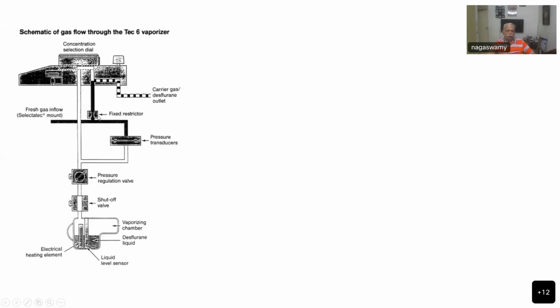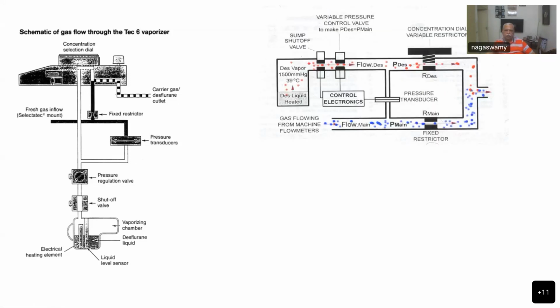So to achieve that, you require a fixed resistor here, and the carrier gas with the desflurane is sent out through this. So the desflurane vaporizer tubing is entirely different, and it gets only blended with that. And the most important component which determines the percentage is the differential transducer. If you see in this picture, you will be able to understand better. So this is the gas flowing from the machine flow meter. It goes through that. There is a resistor here, and there is another separate pathway through which the desflurane vapor is coming.